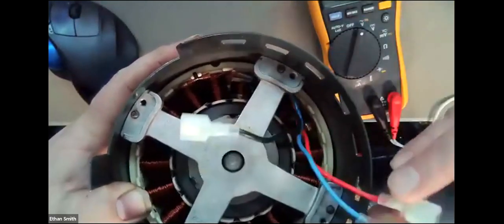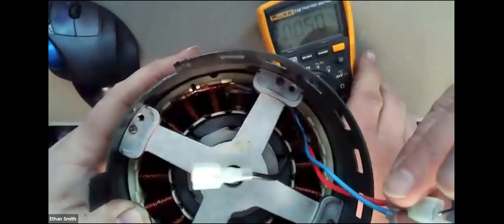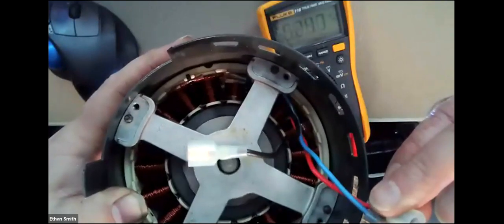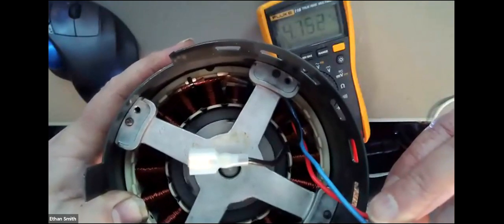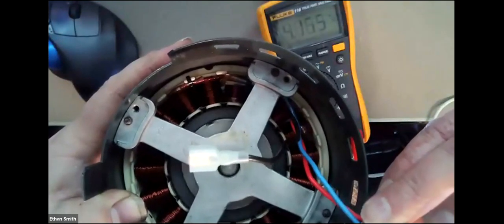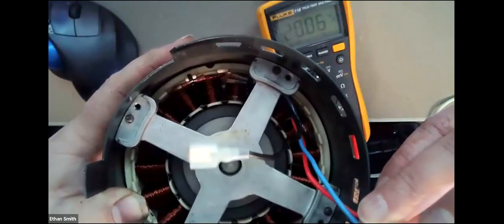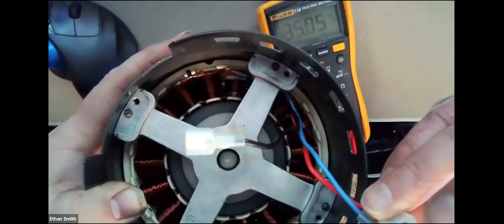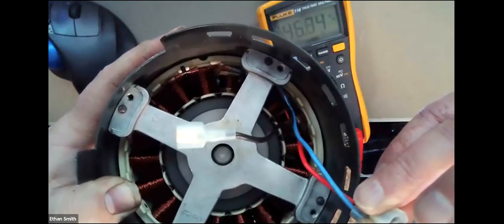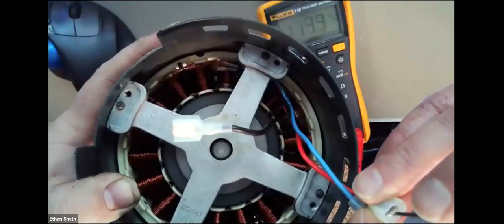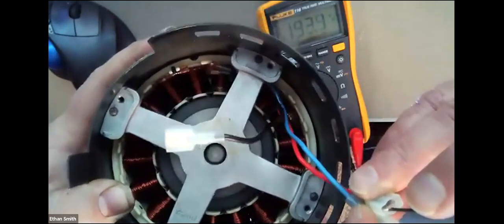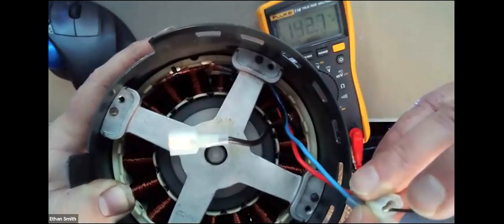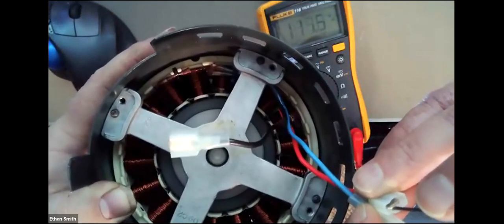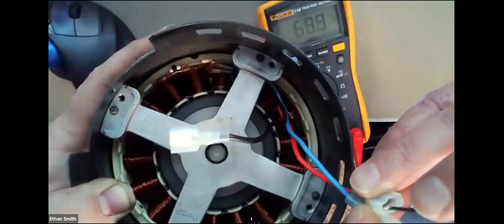I've got a drill on the other side of this motor. And we've got Keith there with the leads in. There's our meter. As I spin this motor, you can see those magnets spinning around. We're starting to get some voltage. We're spinning it rather slow, so we don't get very much voltage. As I speed up, we start to see that voltage climb. In fact, if I take this drill all the way to the top, we've actually got 192 volts. As we reduce the speed, that voltage drops proportionally to how fast we're moving those magnets around.